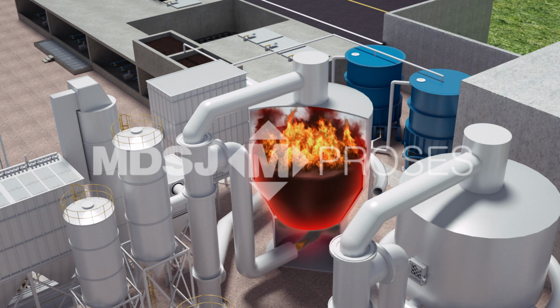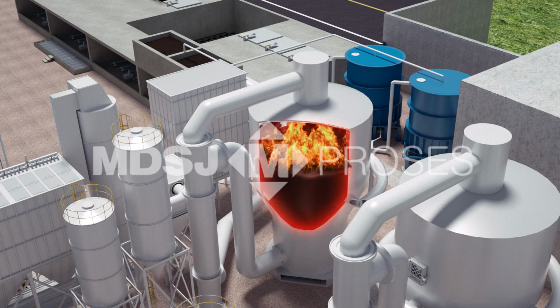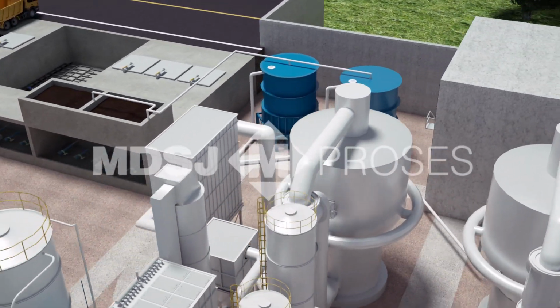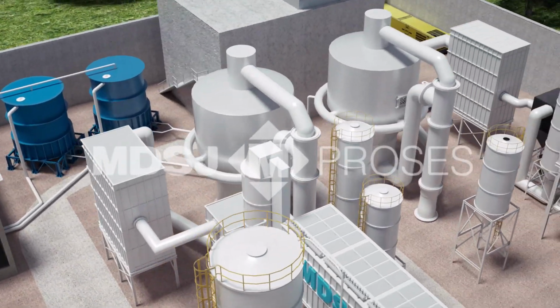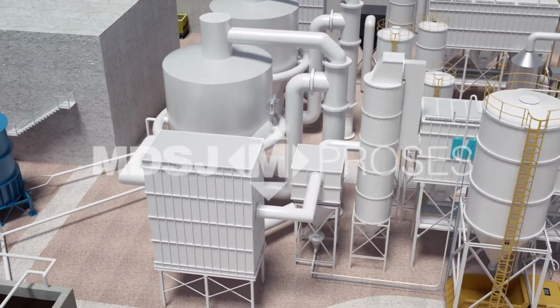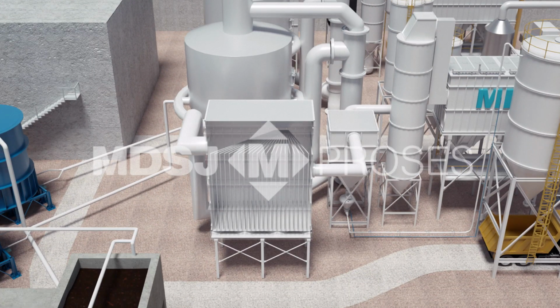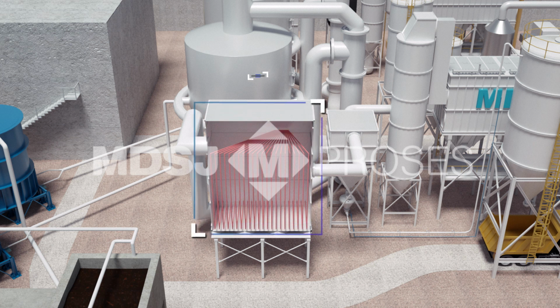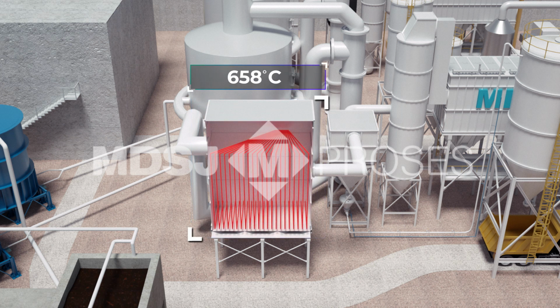Hot flue gases leaving the incinerator first go through a primary heat exchanger, and the fluidizing air coming from the air blowers is heated up to 588 degrees Celsius. This way, the continuity of the combustion is established. After leaving the primary heat exchanger, the flue gas temperature is reduced to 658 degrees Celsius.